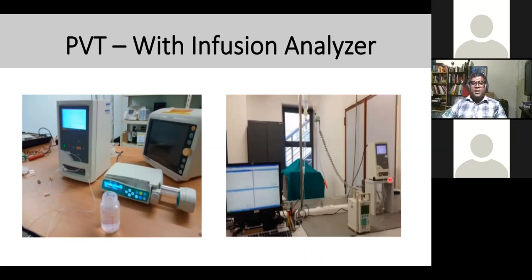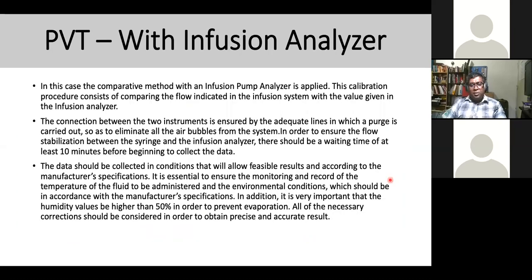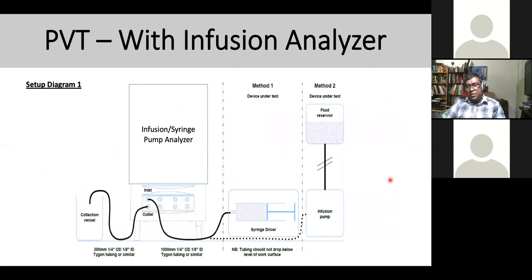You see the flow rate on the infusion analyzer itself. So you can do the infusion flow, all this, and you can see the connection looks like this. For infusion, there's a connection to the infusion analyzer and going to the waste, basically the outlet. For the syringe, also the same connection. By using this setup diagram, you can do flow rate, time, occlusion pressure, everything in this particular device.